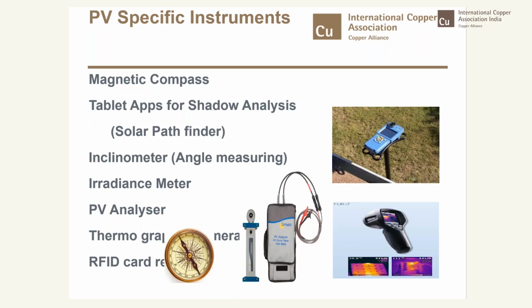You need to have a magnetic compass to identify the orientation. You need a tablet app for a shadow analysis locally. Earlier, we used to have Solar Pathfinder, which is now being mostly replaced by applications. We have inclinometers for measuring the tilt angle of the module, and we need an irradiance meter to check the radiation level at the site, the direct normal irradiance at the site.